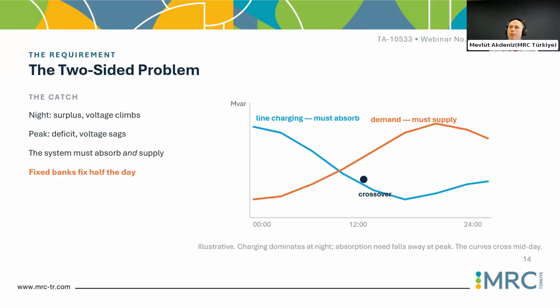So the main issue is based on reactive power and voltage regulation, but the solution pathway could be different depending on the network topology itself, which is also related to the country-specific generation fleet, daily load curves, and the geographical spread of the network in the country. So excess line charging is a problem at night with long lines, especially high voltage lines, or even with medium range cables. We may have excess charging reactive power here.